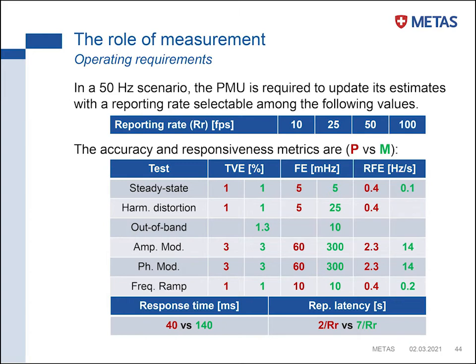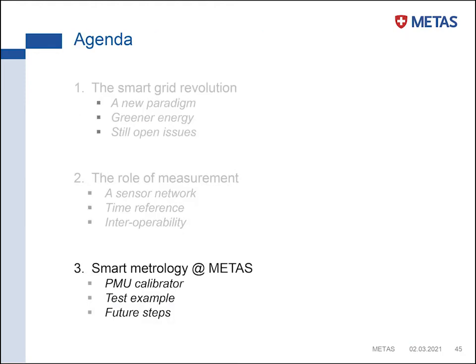These are the requirements, so they are not interesting for us in this context, but I just wanted to give the idea that the PMU normally, in our scenario, will work giving from 10 up to 100 estimates per second. And the latency depends on how fast the PMU is, but if we work at 50 or 100 frames per second, we want for the protection class no more than 20 milliseconds latency. That is not impossible to achieve, but is quite challenging.